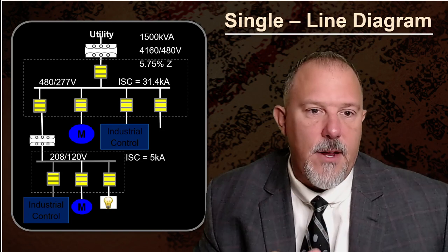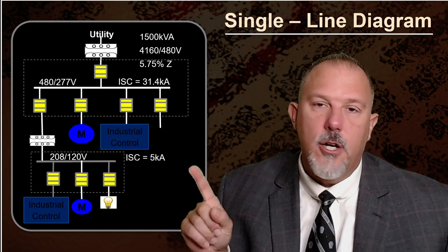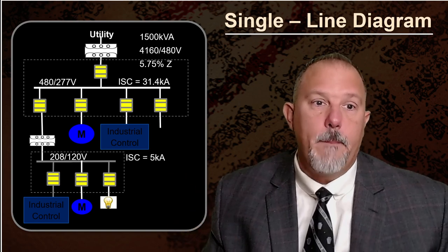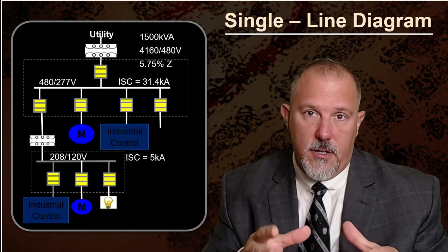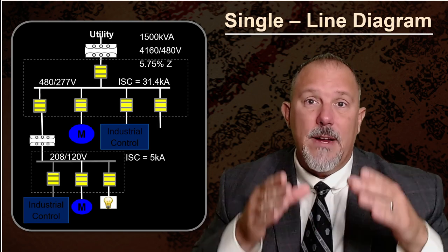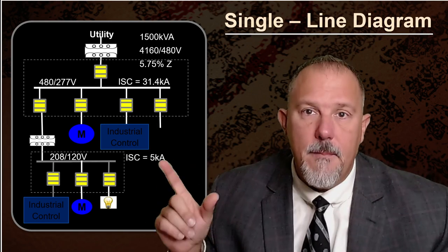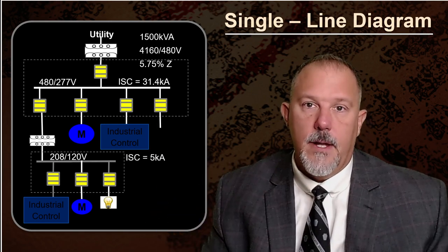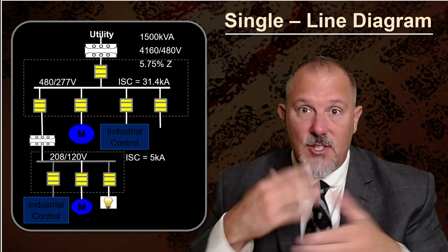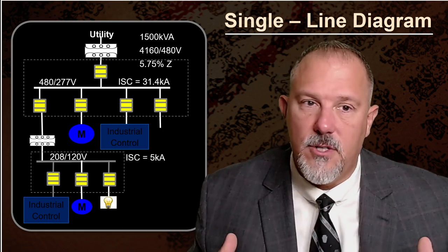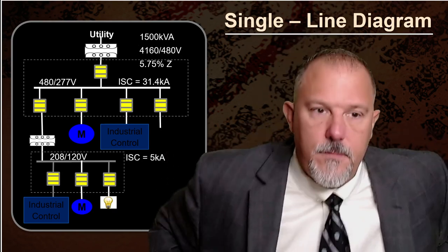Why did my severity for incident energy go up? Because I'm on the secondary of that transformer, because the overcurrent device that I'm relying on for incident energy reduction is on the primary of that transformer. How do I pick that? Now, this is all about the qualified person. Think about what I'm talking about.